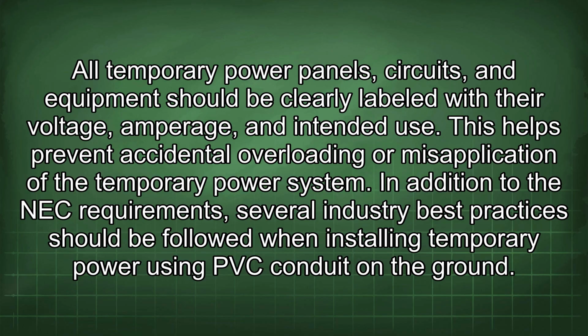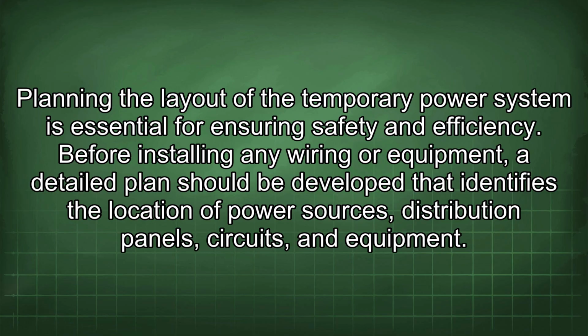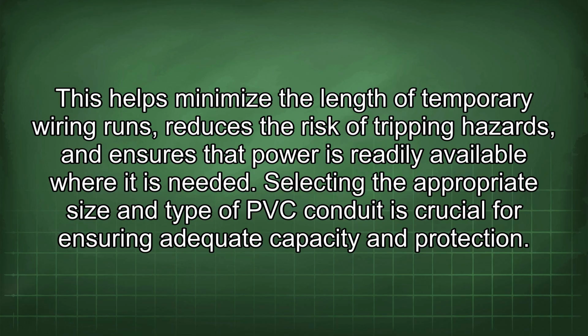on the ground. Planning the layout of the temporary power system is essential for ensuring safety and efficiency. Before installing any wiring or equipment, a detailed plan should be developed that identifies the location of power sources, distribution panels, circuits, and equipment. This helps minimize the length of temporary wiring runs, reduces the risk of tripping hazards, and ensures that power is readily available where it is needed.